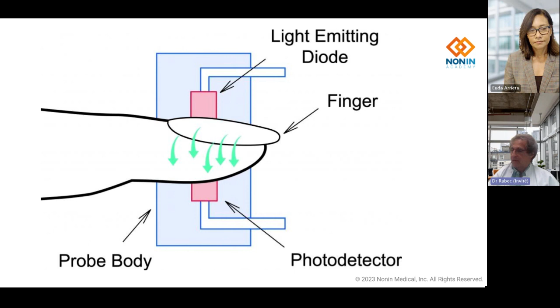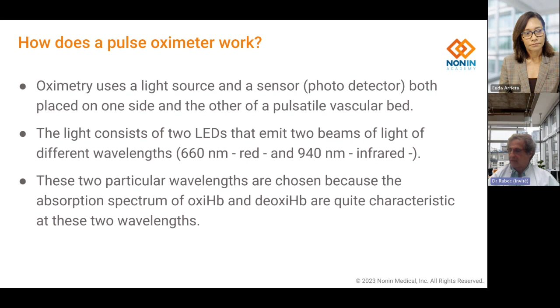Yes, of course. In fact, how does a pulse oximeter work? Oximetry uses a light source and a sensor, a photodetector, placed on one side and the other of a pulsatile vascular bed. This light consists of two LEDs that emit two beams of light of different wavelengths: 660 nanometers for red and 940 nanometers for infrared. These two particular wavelengths are chosen because the absorption spectra of oxyhemoglobin and deoxyhemoglobin are quite characteristic at these two wavelengths.